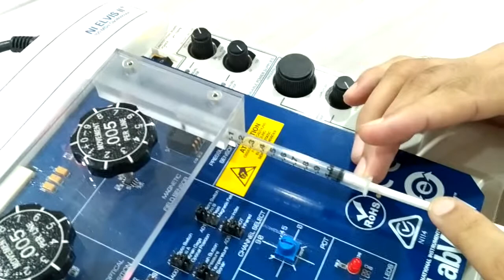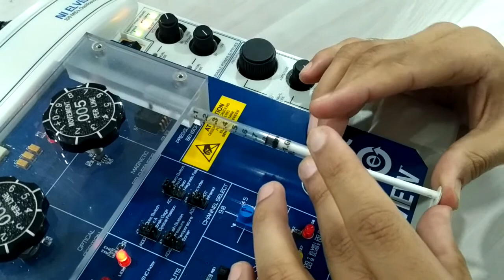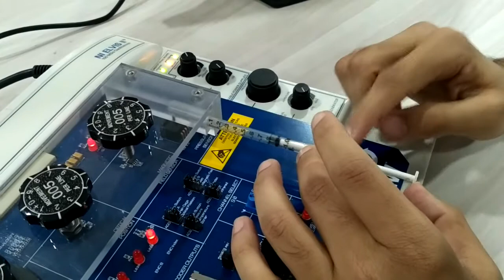Now remember, whenever you are taking the reading, never take your hand off this plunger, because as soon as you move it towards the zero end, there will be some back pressure on the plunger as well. So you have to keep holding the plunger while taking the reading. This precaution you have to take. So now it is at 0.8 ml.